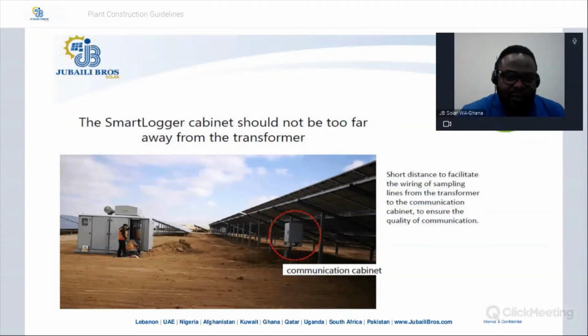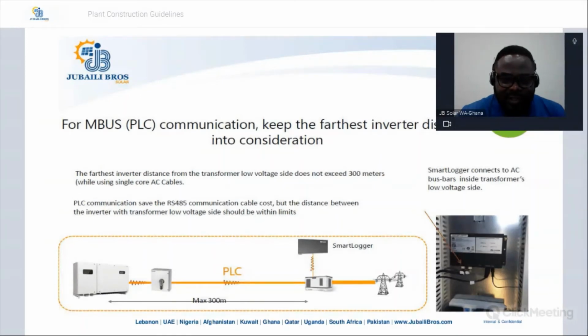And also, normally, let us always make sure that the smart logger cabinet should always be closer to the transformer if there's one. Let's go back to the PLC. So here you see that this is a transformer, right? So if you are doing a project where there's a transformer and there's a smart logger unit, the smart logger unit will normally be part of something we call a SACU, a smart array controller unit. So if the smart logger is inside the smart array controller unit, this array controller unit must be connected directly onto the transformer. There's a position around the transformer where we allow you to put the smart logger directly onto the transformer. It shouldn't be away from it.